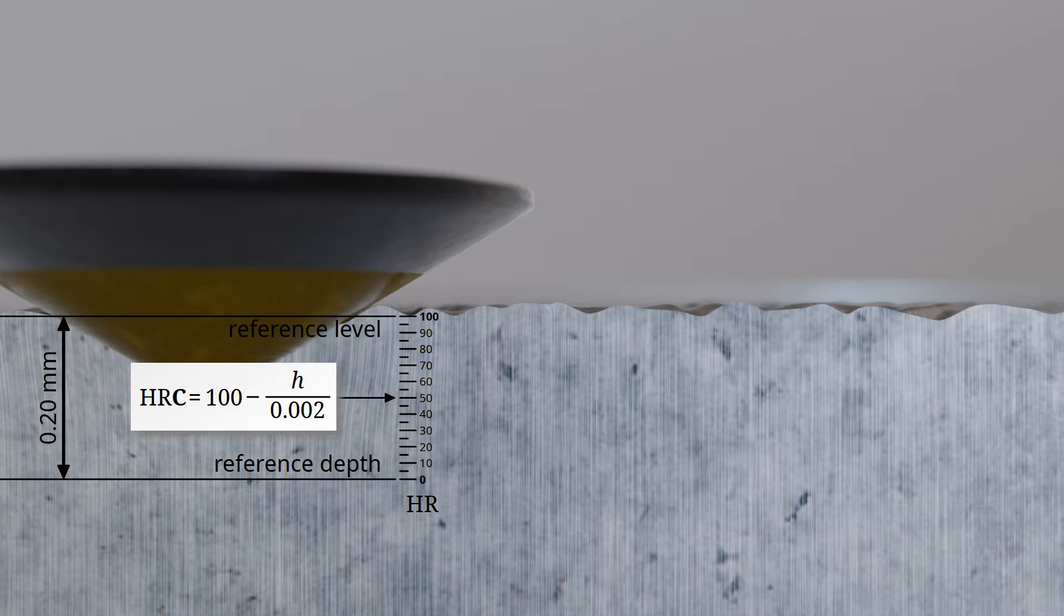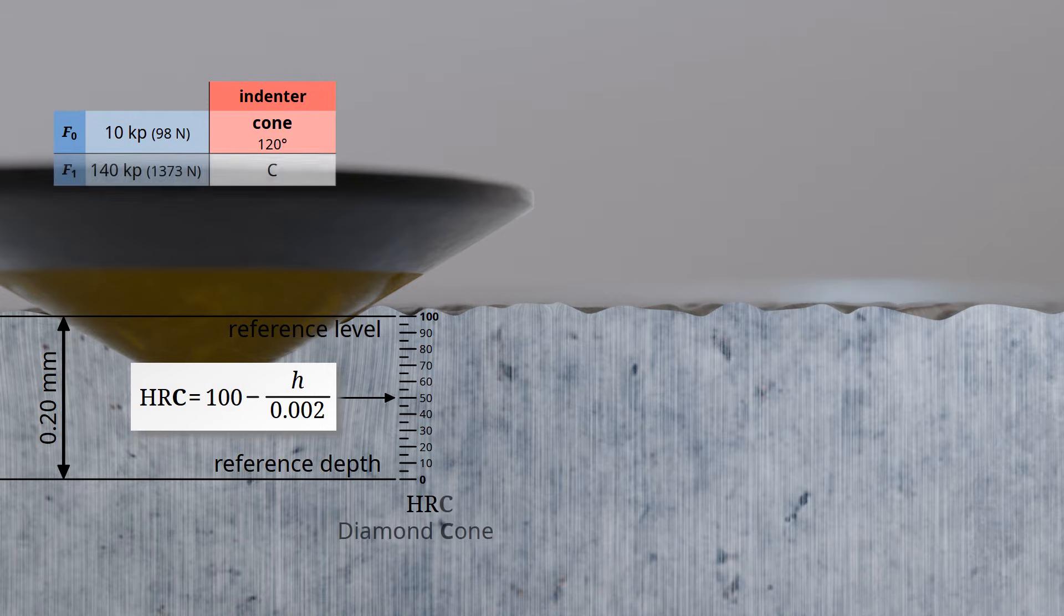With the exception of special procedures, the preload is 10 kiloponds, equivalent to 98 newtons. Depending on the specific test variant, different test loads are applied. In the so-called test variant scale C, the sample is subjected to a test load of 140 kiloponds, which corresponds to 1373 newtons.